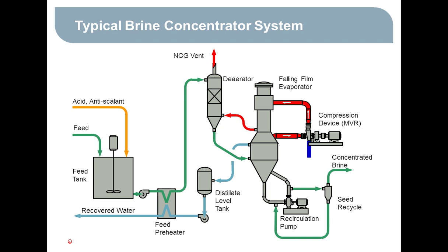And then the feed goes up to a deaerator. And the deaerator is where the CO2 that was created in the feed tank is stripped out along with any dissolved oxygen. And that's to keep the evaporator, which is the next piece of equipment, from corroding by taking those oxidizing atmospheres out of there. The actual evaporation occurs in a falling film evaporator, which is driven by a mechanical compressor, which pressurizes the water vapor and raises its temperature. When you pressurize water vapor, you raise its temperature. And so that hotter water vapor can be used instead of external steam as the heat source for the evaporator.